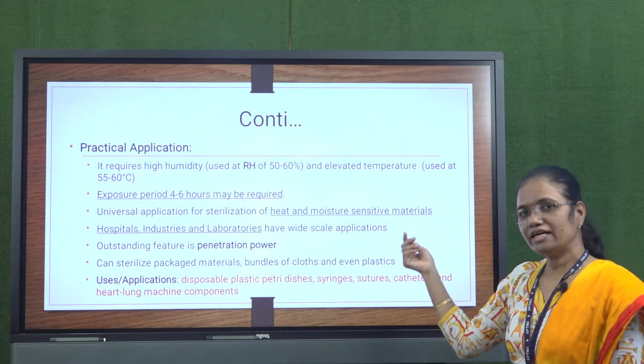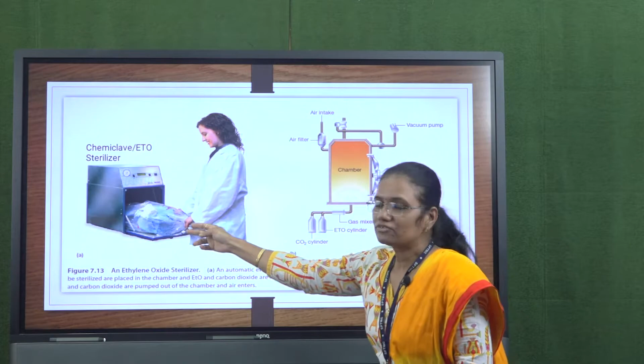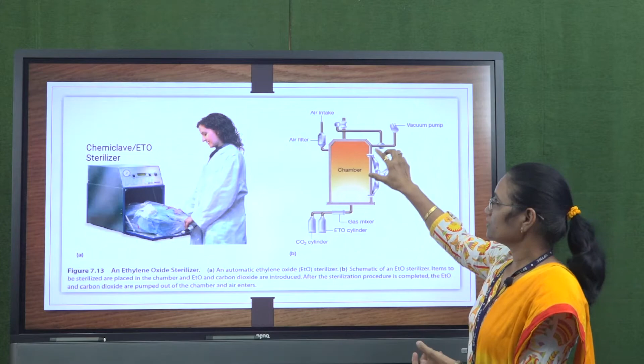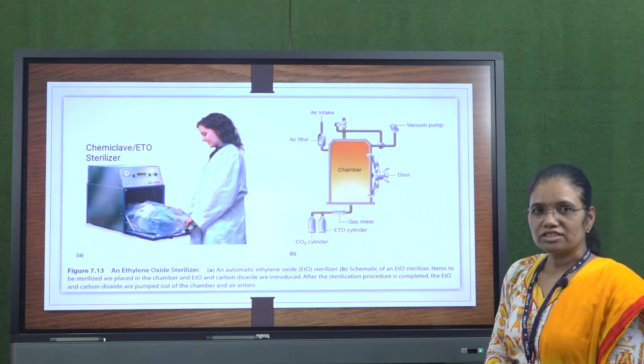This is a schematic diagram of the ethylene oxide sterilizer, also called a chemiclave, and you can have a look at how this instrument looks. As you can see here, materials after packaging can also be sterilized in this sterilizer. The thing to be checked here is the proportion of the diluent gas and ethylene oxide, which is to be maintained in a closed chamber. At the same time, you have to maintain the relative humidity and temperature in the chamber. After the sterilization process is over, which requires 3 to 5 hours depending on the load and the microbial content, we have to remove the ethylene oxide completely from the chamber and flush in fresh air so that complete removal takes place, as it is toxic to human beings also.